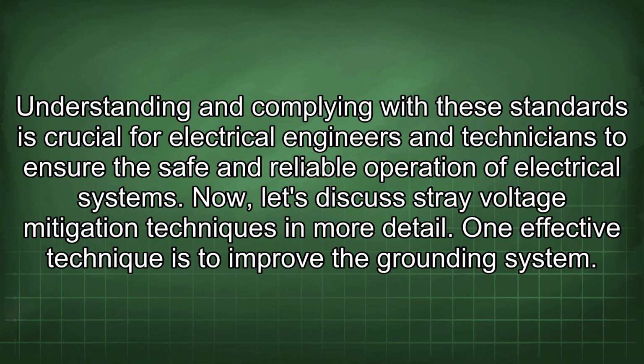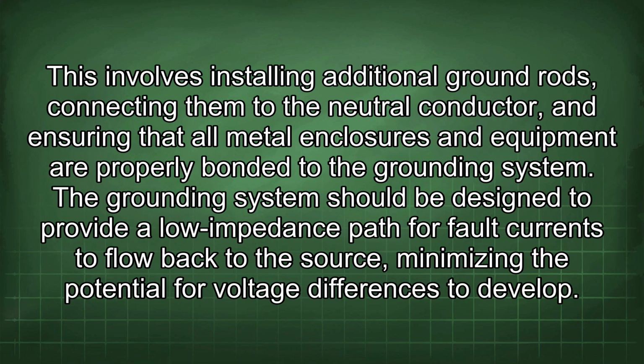Understanding and complying with these standards is crucial for electrical engineers and technicians to ensure the safe and reliable operation of electrical systems. Now let's discuss stray voltage mitigation techniques in more detail. One effective technique is to improve the grounding system. This involves installing additional ground rods, connecting them to the neutral conductor, and ensuring that all metal enclosures and equipment are properly bonded to the grounding system. The grounding system should be designed to provide a low impedance path for fault currents to flow back to the source, minimizing the potential for voltage differences to develop.